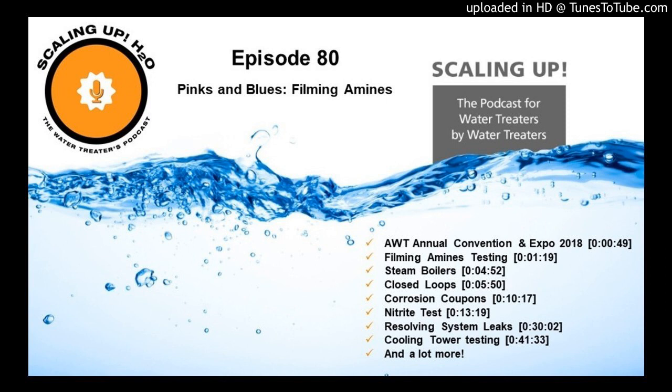So if it was 120,000, we added 1 pound, it would be 120,000 divided by the change of sodium nitrite that your 1 pound got you. So what that is, it's the final sodium nitrite result that you got in parts per million minus the initial result that you got in parts per million. Now that's the delta. So if you just wanted to say it's 120,000 times the pounds you added divided by the change of sodium nitrite, and then you just simply divide that through.